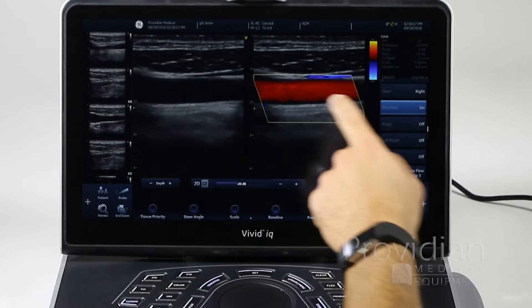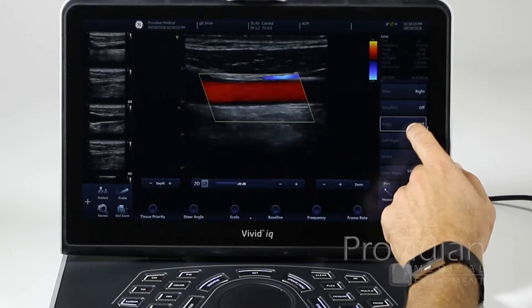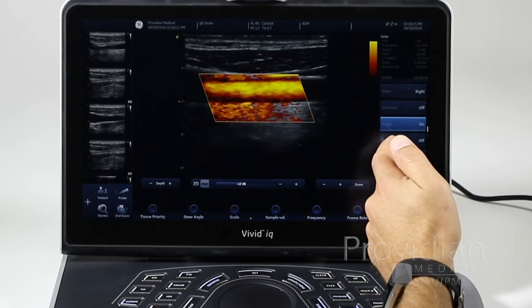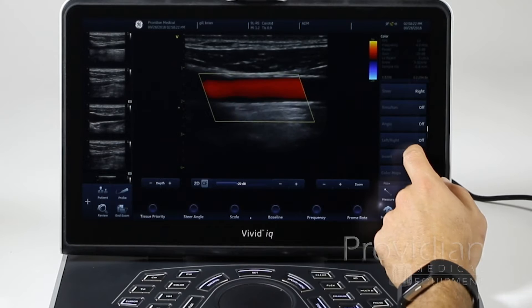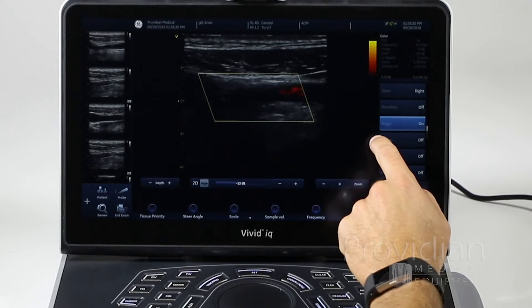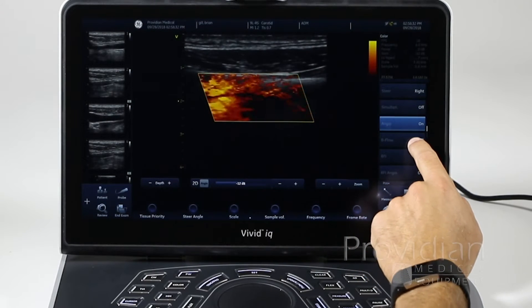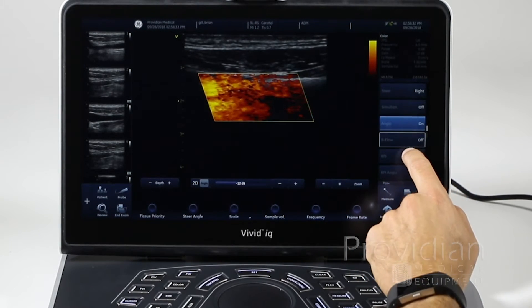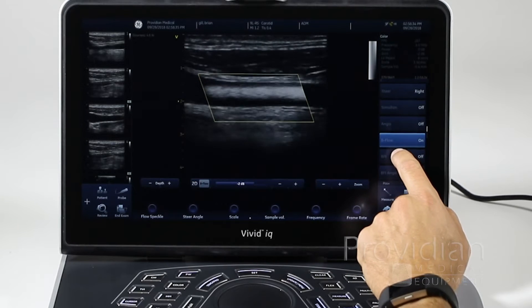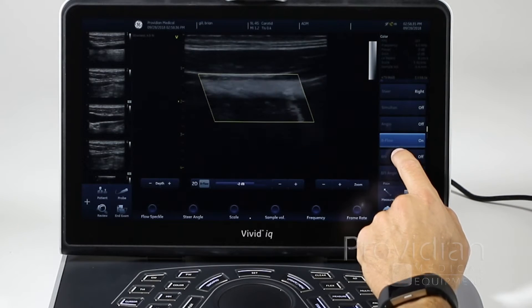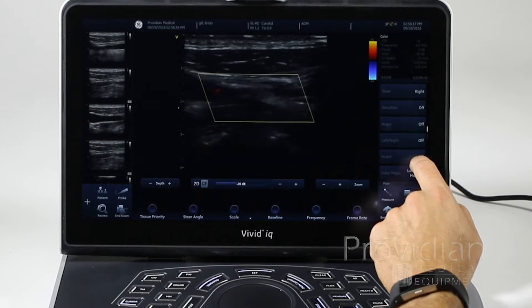Simultaneous gives you a B-mode and a color. Angio is your power Doppler, on or off. And also with your Angio, you get this B-flow, where you get the flow in the 2D imaging. I can turn that off.